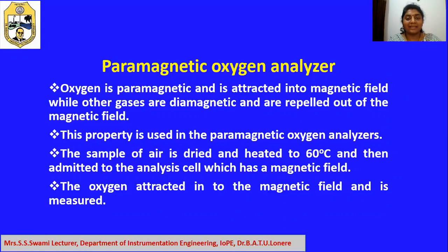The name itself indicates that paramagnetic means attraction towards the magnetic field, while others are repelled from the magnetic field. So this property is used in paramagnetic oxygen analyzers.